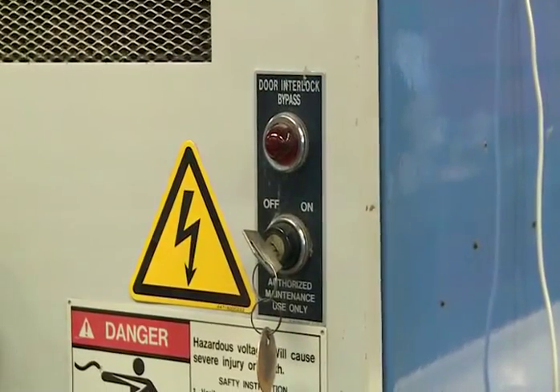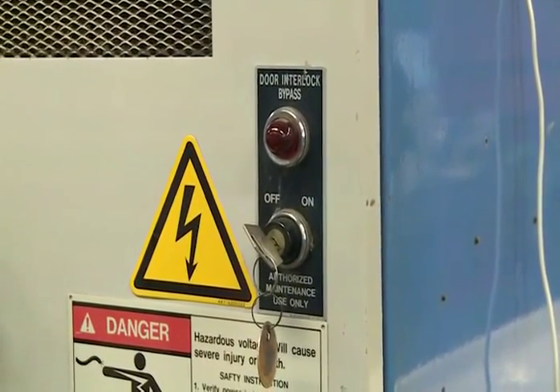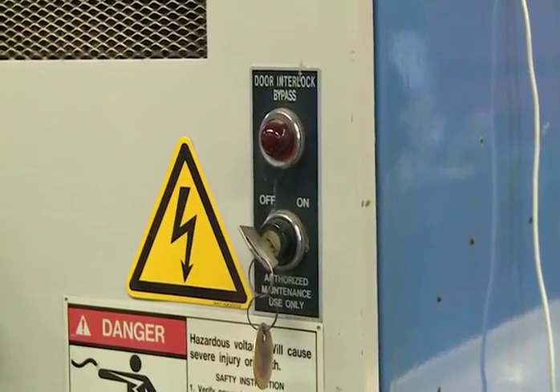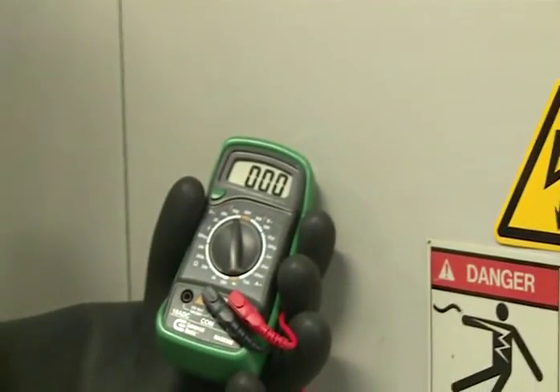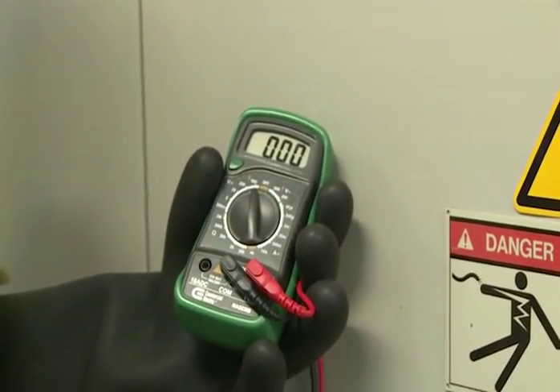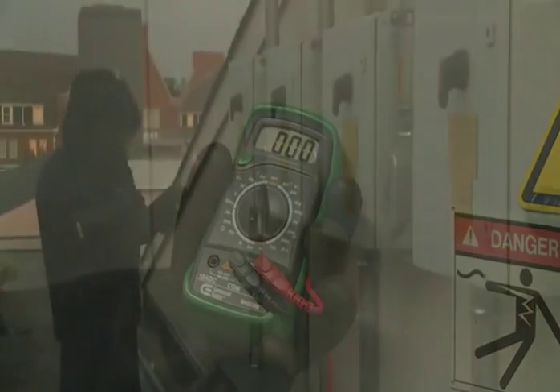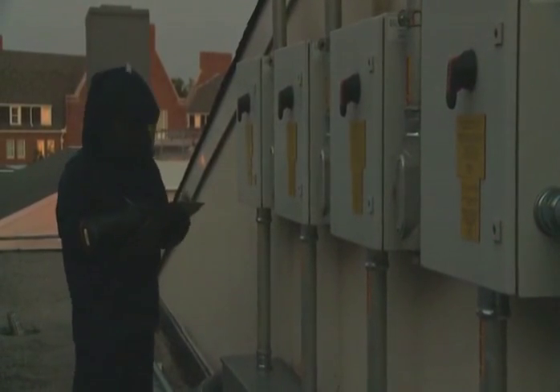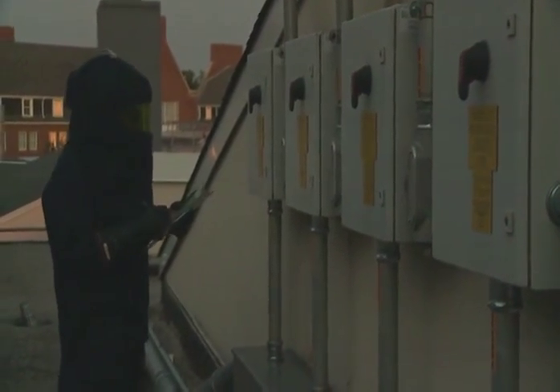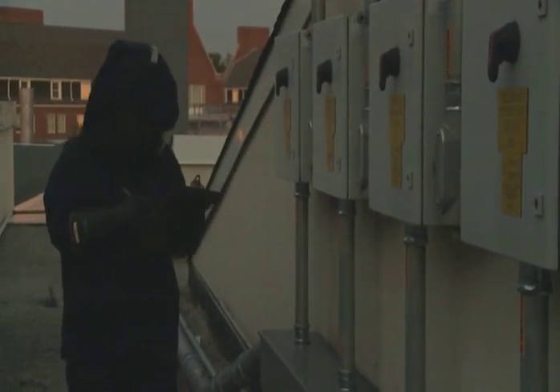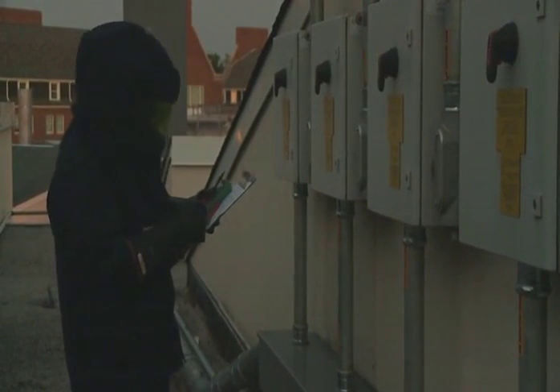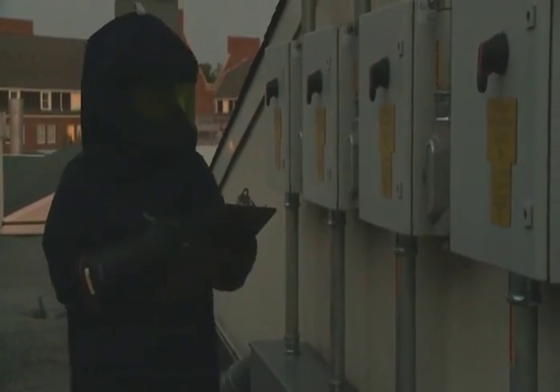But the equipment must still be treated as if it's energized and a potential arc flash hazard until it has been tested to make sure the power really is off. This means that the electrical workers who are servicing the equipment must continue to adhere to safe work practices and wear protective clothing and PPE even when they conduct the test.